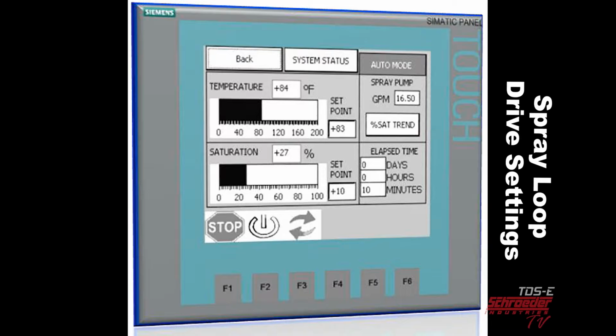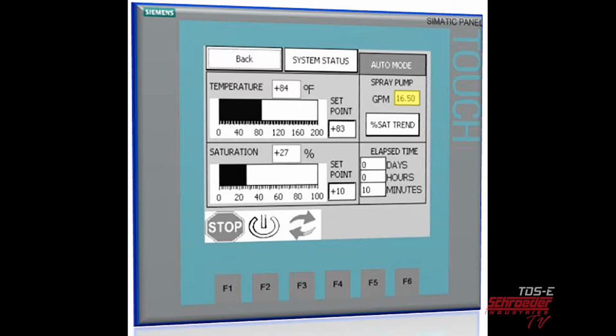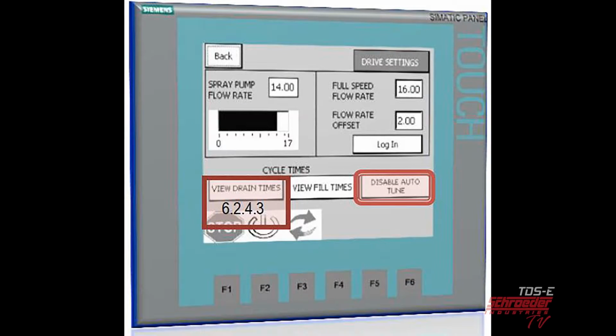The spray loop drive settings screen can be accessed by pressing GPM in the auto mode screen, the status screen, or the manual mode screen. This allows users to view the cycle time history. Cycle time history can be viewed by pressing one of the buttons on the bottom left half of the screen. Each time the power is cycled, the default auto-tuning function will be enabled. This function uses the cycle time history data to synchronize the pump speeds. Users can disable the auto-tuning function by pressing the Disable Auto-Tune button located on the bottom right half of the screen. With a user's password, the flow rates can be adjusted in the following ranges: full speed flow rate from 15.5 to 16.5 GPM, and flow rate offset from 2 to 5 GPM.